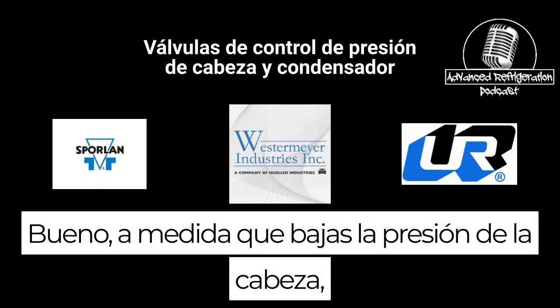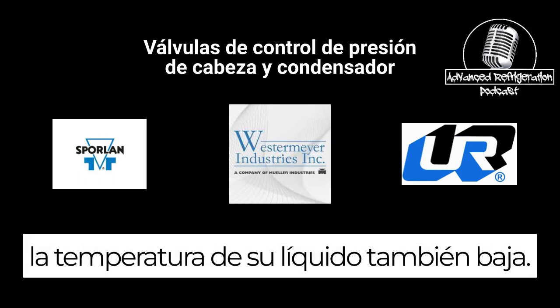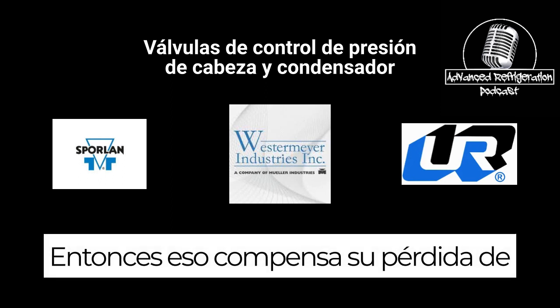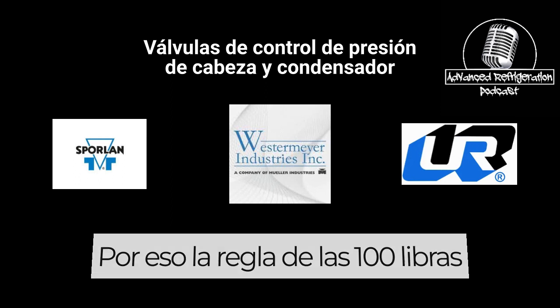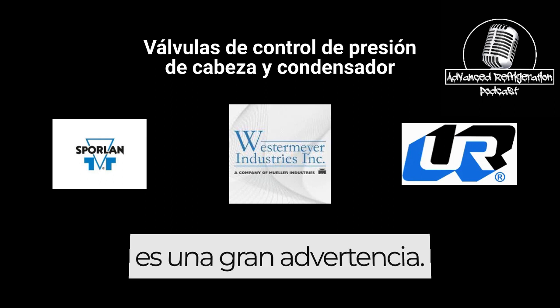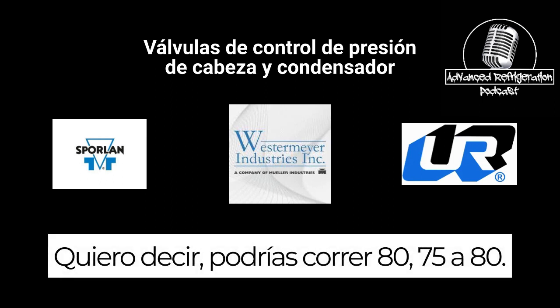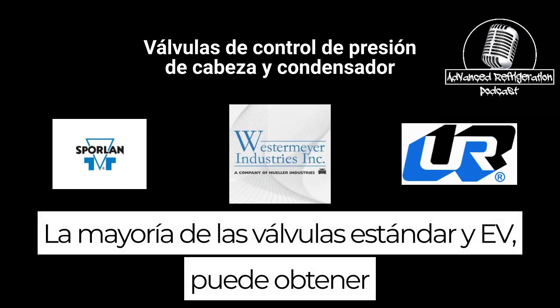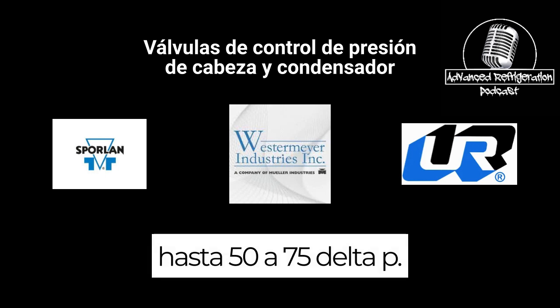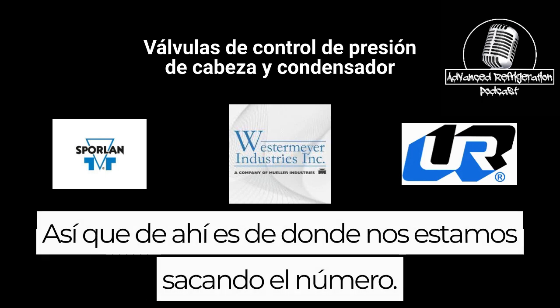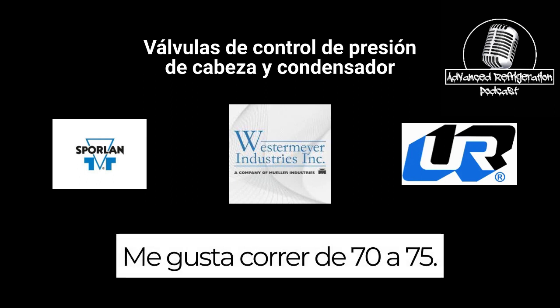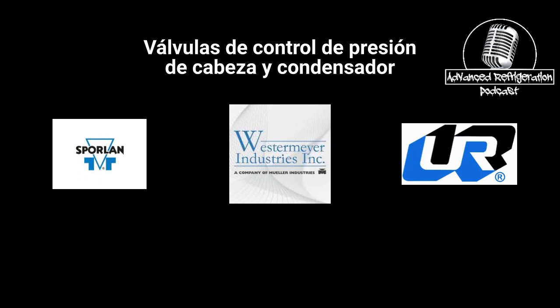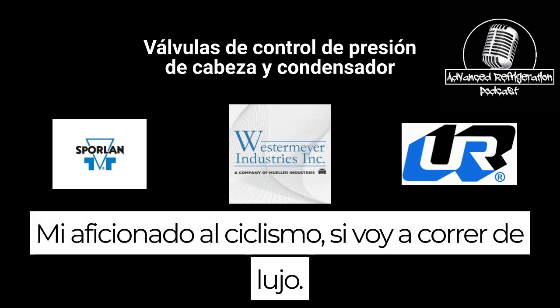As you lower your head pressure, your liquid temperature also comes down. So that offsets your loss from your delta P in most cases. That's why the 100-pound rule is so much of a caveat. You could run 75 to 80. Most standard valves and EEVs, you can get down to 50 to 75 delta Ps. So that's where we're coming up with that number. I like to run 70 to 75 on my fan cycling if I'm going to run fan cycling.